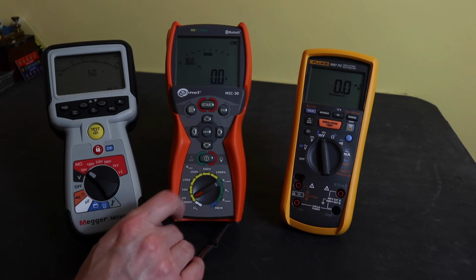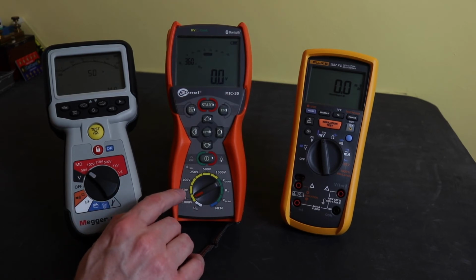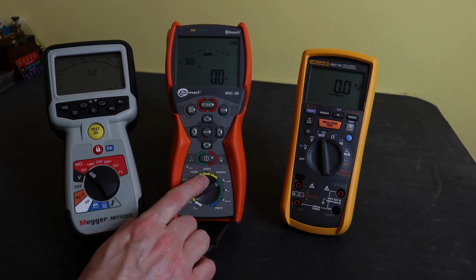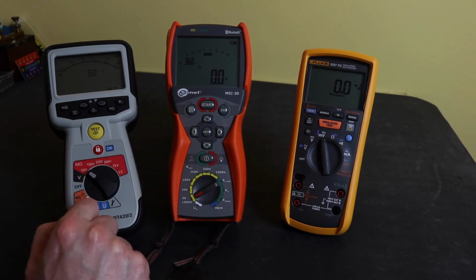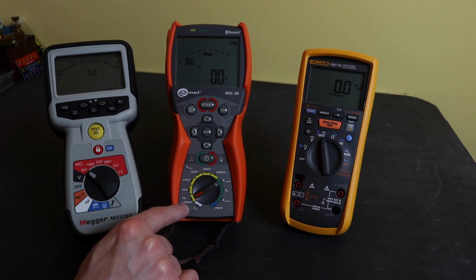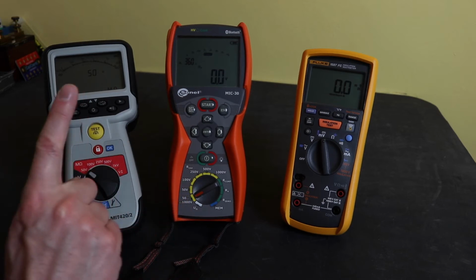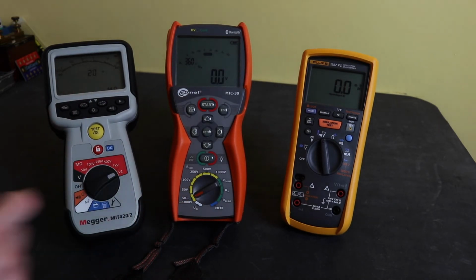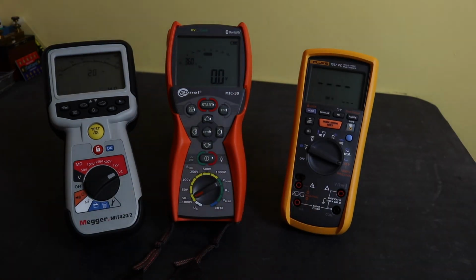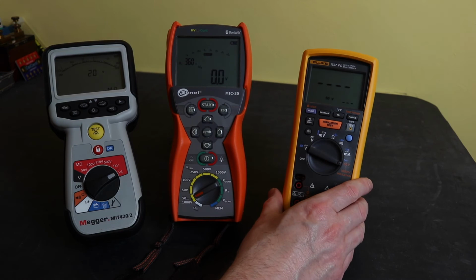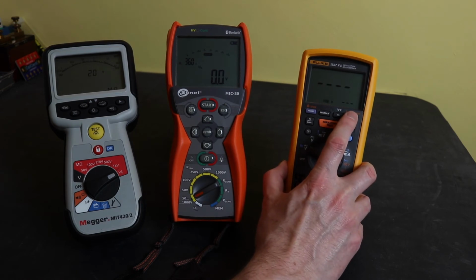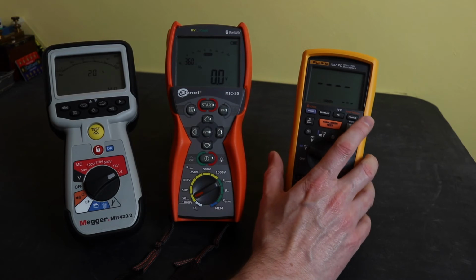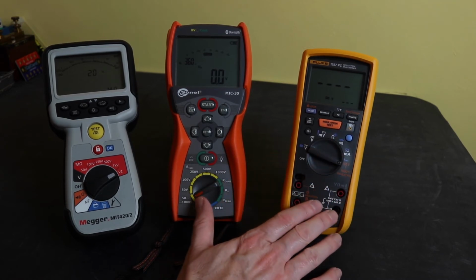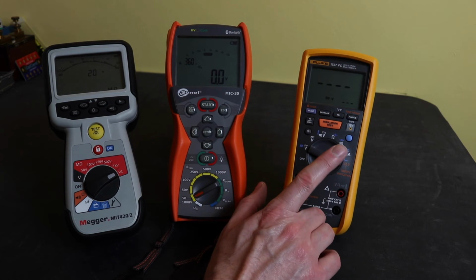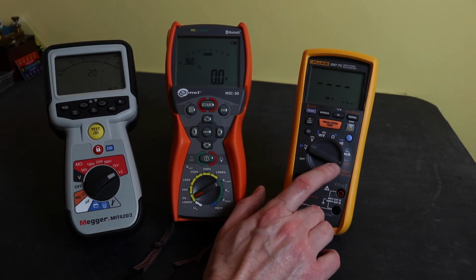With both of these two instruments, there is a fixed setting for each of the positions, 50, 100, 250, 500, 1000. Same for the Megger here. The initial position is a 50 to 1000 volt variable voltage function on the Sonel. For the Megger, the variable voltage function is around here at the end. On the Fluke over here, the voltage selection is electronic. Again, you've got 50, 100, 250, 500, 1000. So same test voltages, just electronically selected. There is no variable voltage function on this instrument.